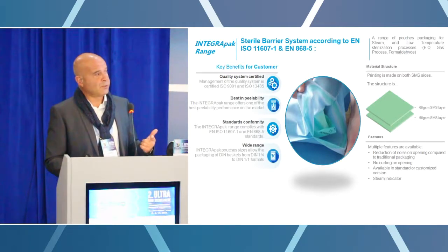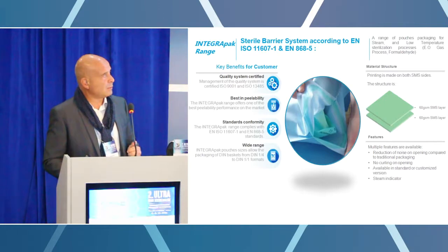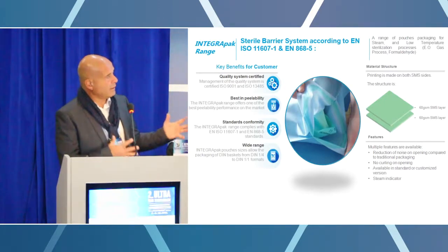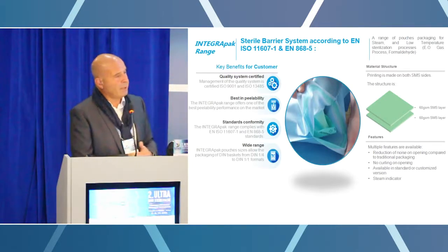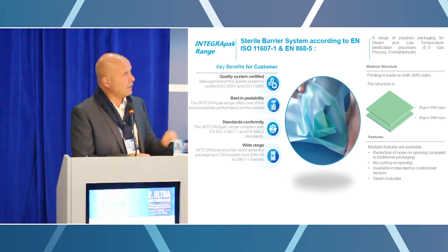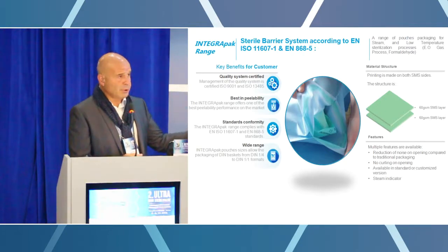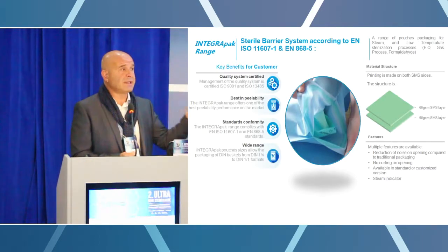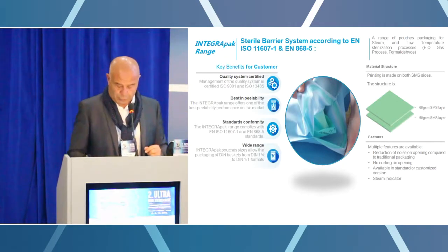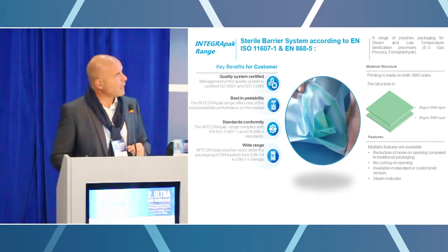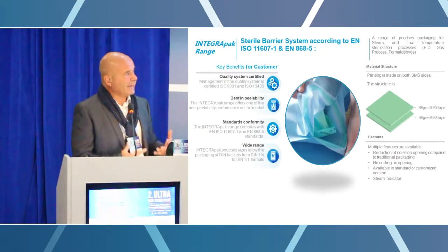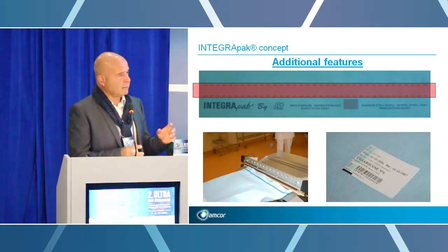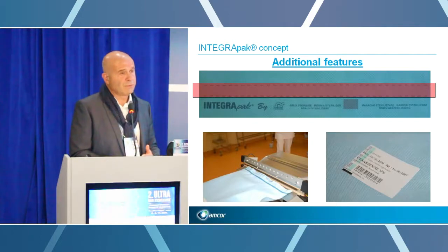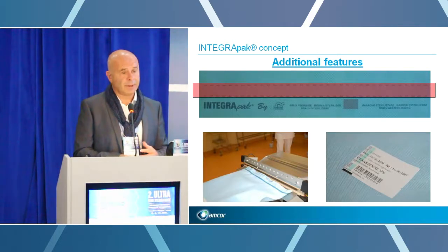Because if you have long storage, the risk is very important. These are the characteristics of this product. It's possible to have a part of the sealing, and it's very easy to determine when you do the seal. You need a special machine because it's not possible to use the rotary sealing machine for this material. It's just an impulse sealing machine, and it's possible to put the label on this. IntegraPack is a first packaging with a strong resistance and a conformity in pouch. It conforms with 11607 part 1, and part 2 for the control of the closure. Okay?